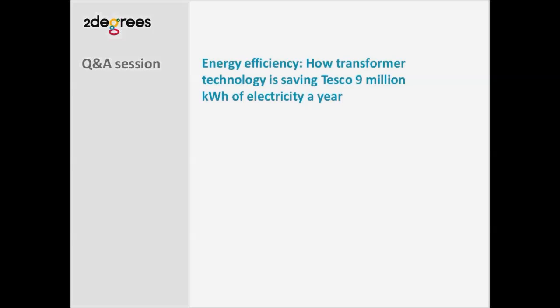Another one here. Do you need to get permission from the energy supplier or involve them at all in the process? Erica, do you maybe want to tackle that one? Well, in most scenarios, you've got. I don't know, Steve, or not? Well, it's going to vary from site to site. It depends if the consumer's got control of their own HV switch, for instance, if it can be isolated on site. That means that it's isolated upstream of the transformer integration, and therefore it can be handled by the approved person on site. Where that isn't the case and the isolation belongs to the distribution network operator, then quite simply you need them. Hope that answers the question.